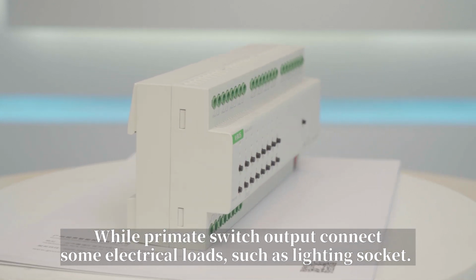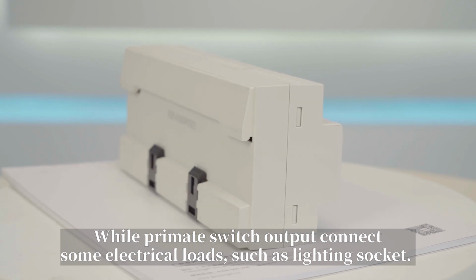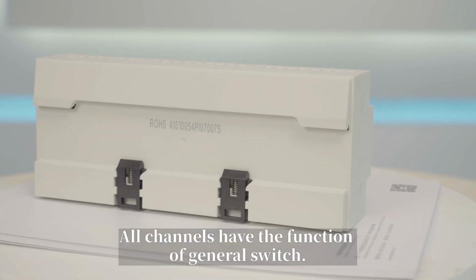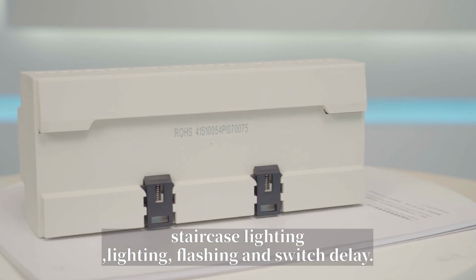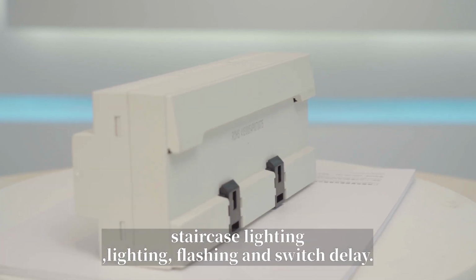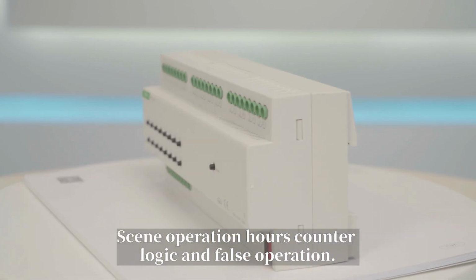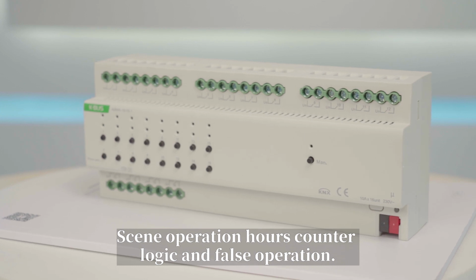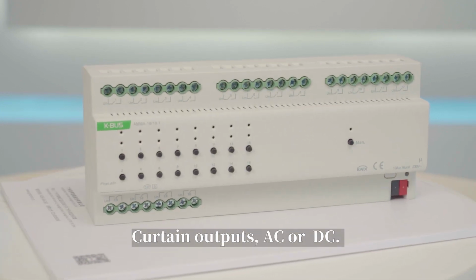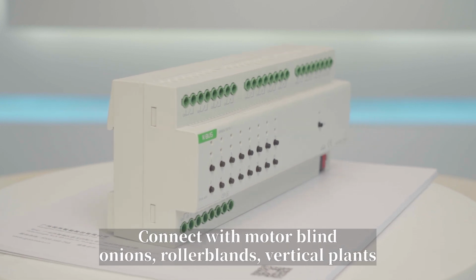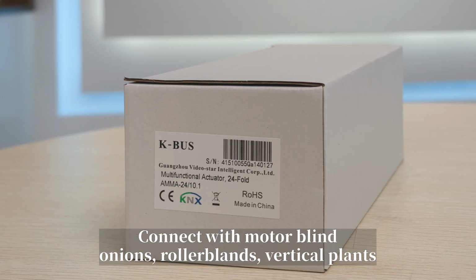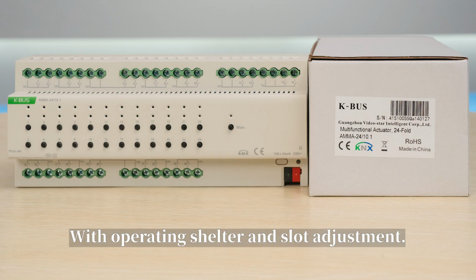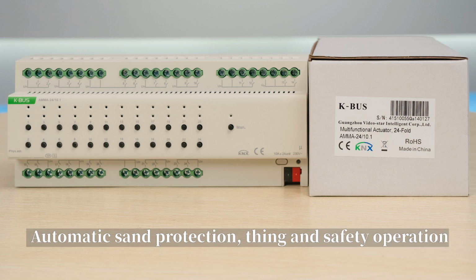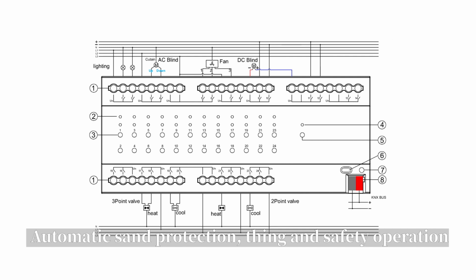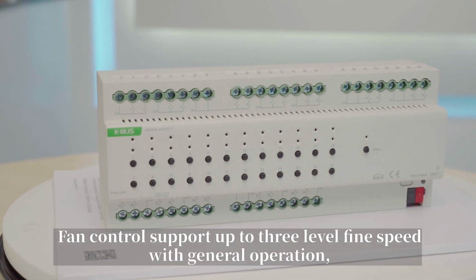Switch output connects some electrical loads such as lighting and sockets. All channels have the function of general switch, staircase lighting, lighting flashing, switch delay, scene, operation hours counter, logic, and force operation. Curtain output, AC or DC, connects with motor blinds, awnings, roller blinds, vertical blinds, etc., with operating shutter and slat adjustment, automatic sun protection, scene, and safety operation, etc.